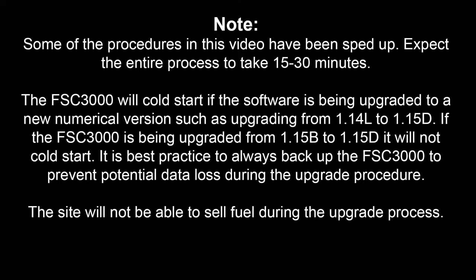If the FSC3000 is being upgraded from 1.15B to 1.15D, it will not cold start. It is best practice to always backup the FSC3000 to prevent potential data loss during the upgrade procedure.